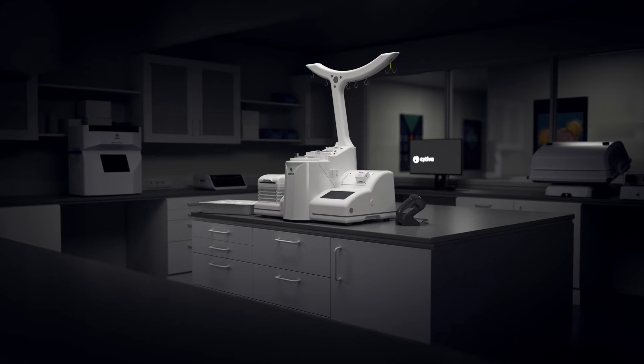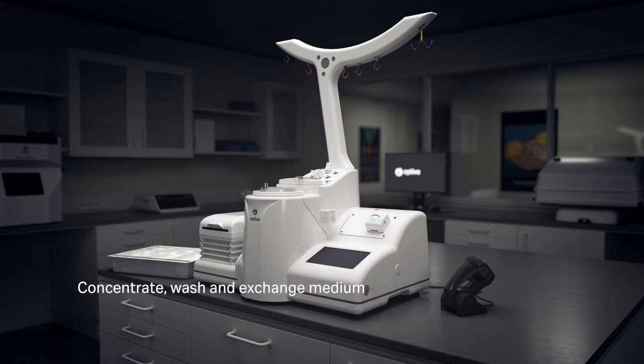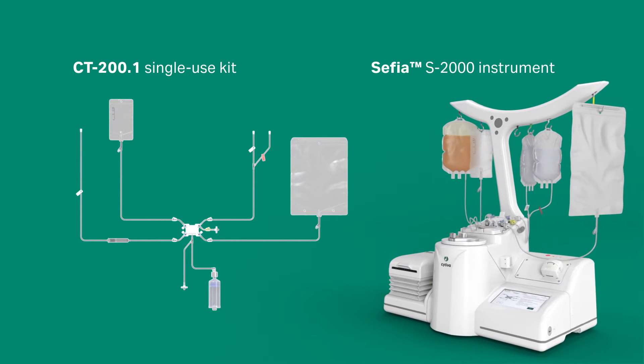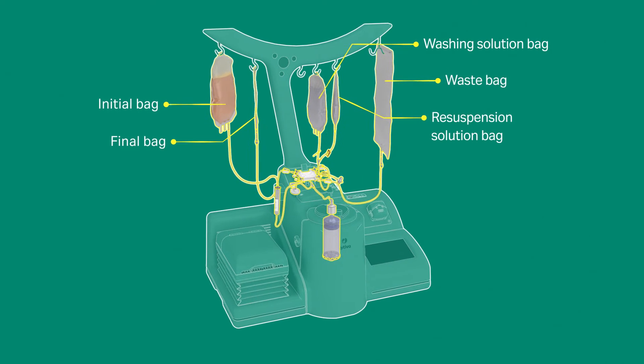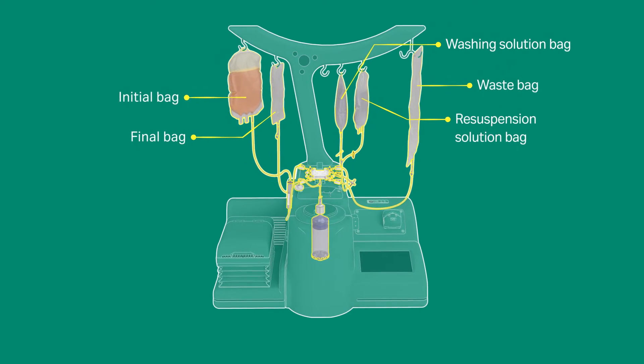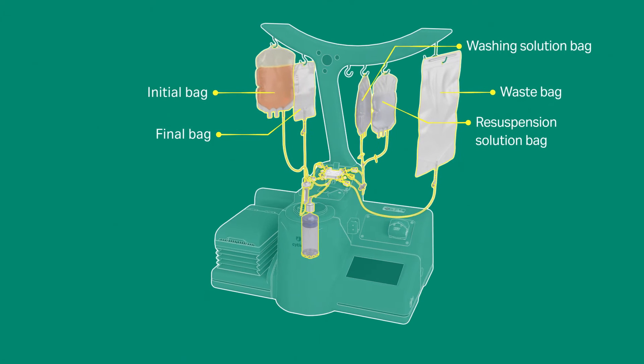S-WASH application is designed to automatically concentrate, wash, and exchange medium from fresh or thawed cellular products. This application works in combination with the Sefia S-2000 instrument and CT200.1 single-use kit. S-WASH automates and closes washing steps from your upstream or downstream cell therapy manufacturing workflow, and can process initial volumes up to 1.2 liters.